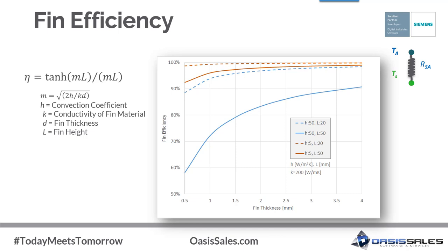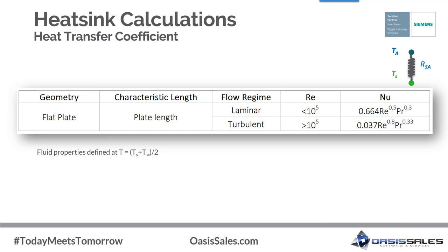As heat conducts into the fin, there is also inefficiency due to the temperature gradient, known as fin efficiency — the ratio of actual heat transfer rate to that if the fin were at uniform temperature. The formula shown assumes the fin tip is adiabatic. The plot shows fin efficiency versus fin thickness for fins at two heights and two heat transfer coefficients, assuming thermal conductivity of 200 W/m·K. Higher heat transfer coefficients for longer or thinner fins yield the lowest efficiency. Fin thickness and material — such as copper versus aluminum — could be considered to address this.